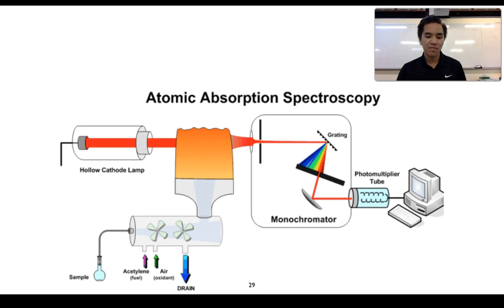The radiation from the cathode lamp is then passed through an atomizer or a reducing flame. So that's this section of our atomic absorption spectrometer. The atomizer is generally made up of a flame or graphite electrodes. Its purpose is to vaporize, which means turn it into a gaseous state, and atomize any metal ions, that is reduce metal ions to metal atoms, in the sample to be analyzed. The sample being analyzed is drawn up through a nebulizer, which mixes it with an acetylene air mixture, sprays the mixture into the atomizer to produce an atomized sample.